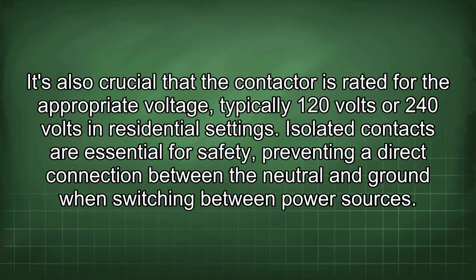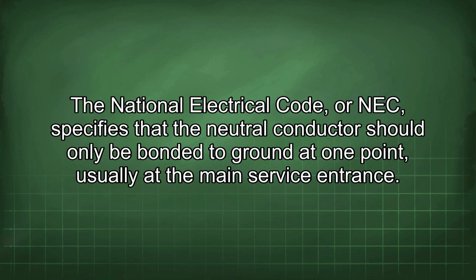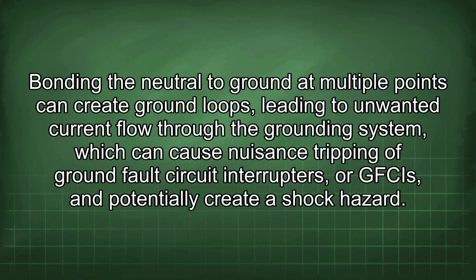It's also crucial that the contactor is rated for the appropriate voltage, typically 120 volts or 240 volts in residential settings. Isolated contacts are essential for safety, preventing a direct connection between the neutral and ground when switching between power sources. The National Electrical Code, or NEC, specifies that the neutral conductor should only be bonded to ground at one point, usually at the main service entrance. Bonding the neutral to ground at multiple points can create ground loops, leading to unwanted current flow through the grounding system, which can cause nuisance tripping of ground fault circuit interrupters, or GFCIs, and potentially create a shock hazard.